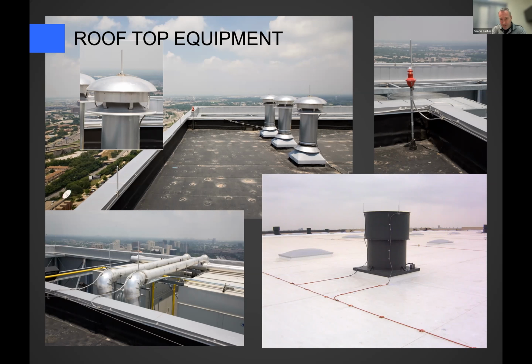But you can see at the bottom right there, there's a big air handling vent coming up. It's protected by 3 lightning rods on it because we always want to stay within 600 millimeters of outside edges and corners. Just putting 1 lightning rod on that big vent is going to leave you probably 1200 millimeters away from the other side. So we want to make sure that we are always leaving 600 millimeters maximum clearance to the outside edge or corner. So if you have to put a number of lightning rods on something to cover it, that's what you do. We do that with big air handlers all the time.